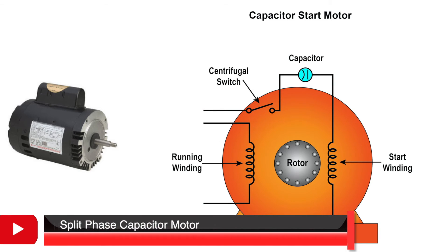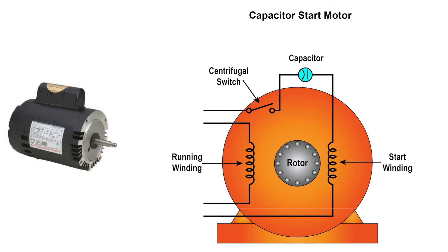Split phase capacitor motors have a capacitor connected in series with the start winding, which creates a phase shift of approximately 80 degrees between the start and run winding. This is substantially higher than the split phase motor and therefore results in a higher starting torque.